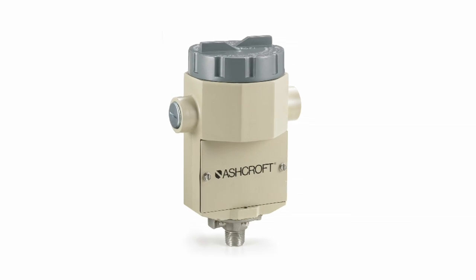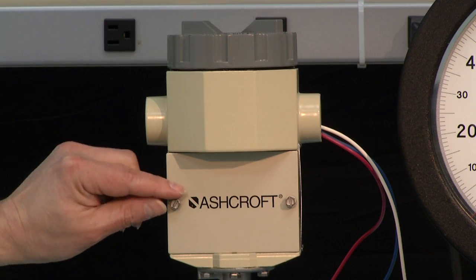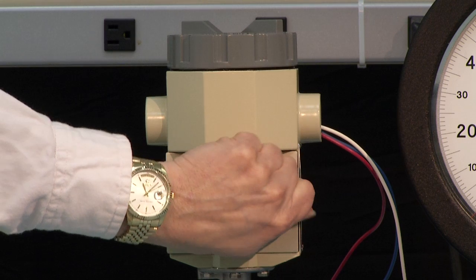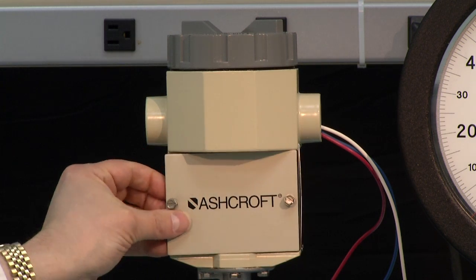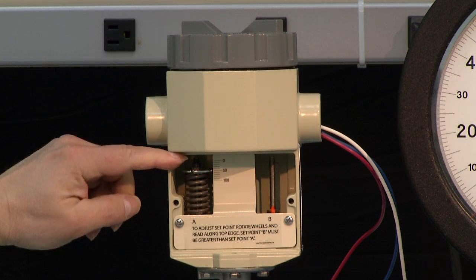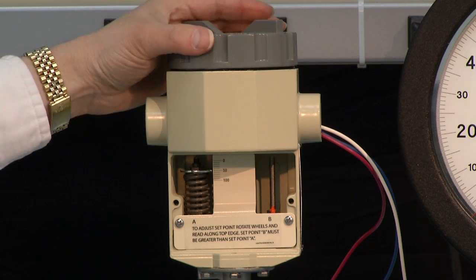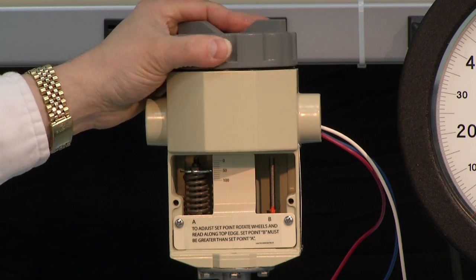The P-Series is a dual chamber design, meaning that the adjustment mechanism, the spring and adjustment wheel, are located in the chamber below, isolated from the electrical. The electrical is located in the top of the switch in the explosion-proof housing.